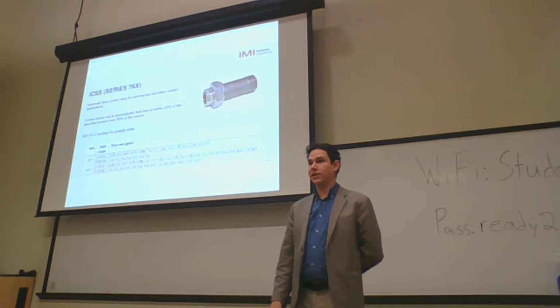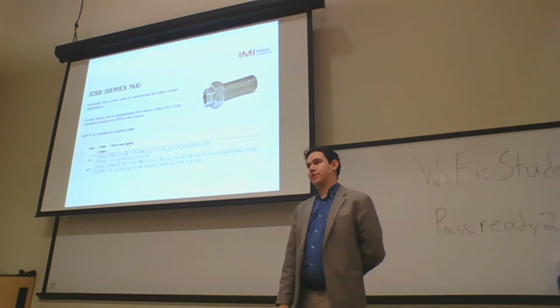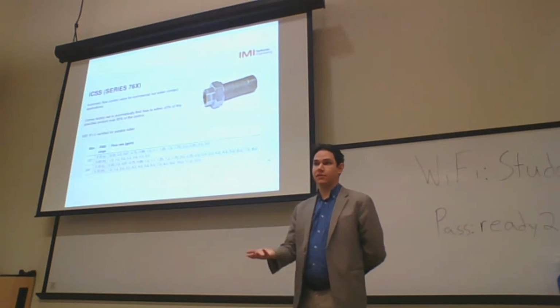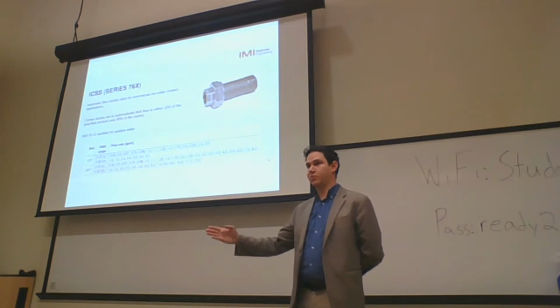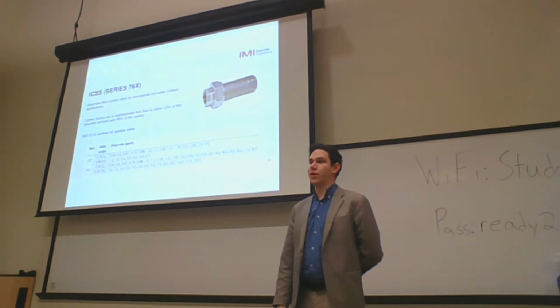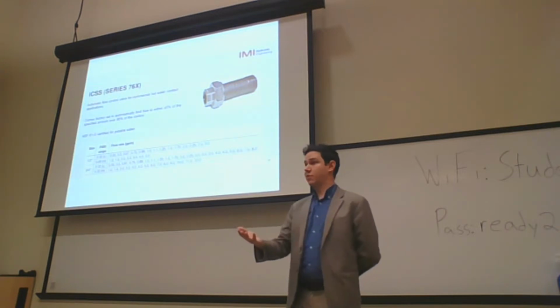0.33 is much better than 0.5 or 1 gallon, but will it solve the problem? If you have 15 sinks down that lane, and you've got 4 lanes, that's a lot of gallons under these circumstances. Depending on how it was designed, if the design took into consideration that you're going to have 0.33 GPM or 0.5 GPM in each recirc line, it worked the same way. But like I said, the best recommendation would be the therm valve.